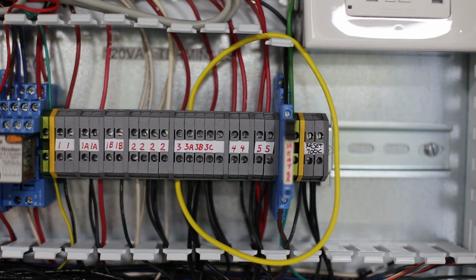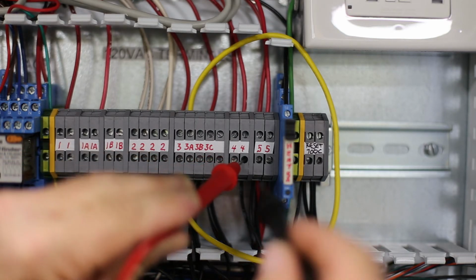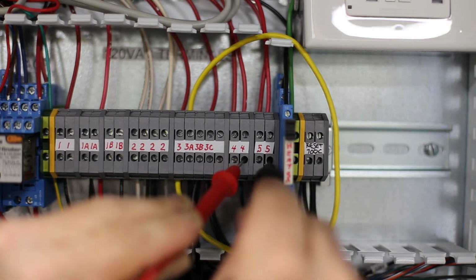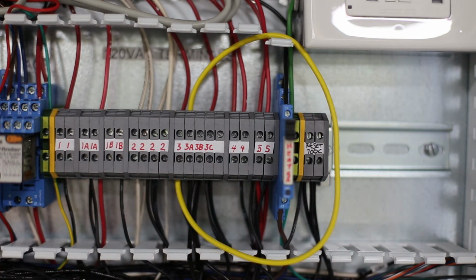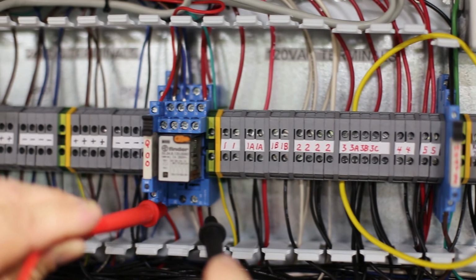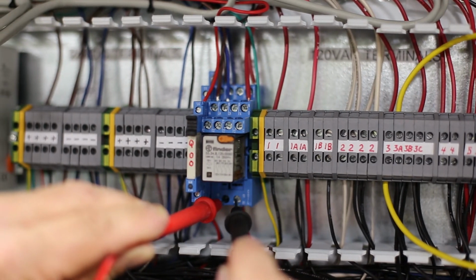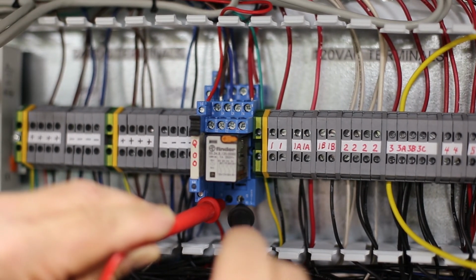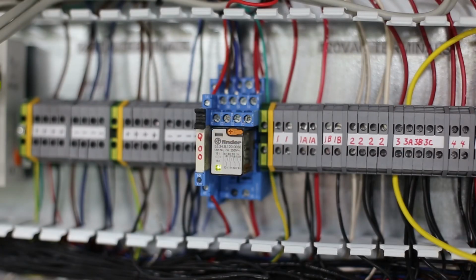In checking for 5, that's part of the start circuit. So as soon as you hit the start button on your machine where the start stop switch is, you should have number 5 come on. And when the number 5 comes on, the start light should come on, and over here to the left is your ACR circuit. And if you check between number 2 and number 5 over here, you should have 120 volts. Also, that light there at the bottom should light up green when that happens.